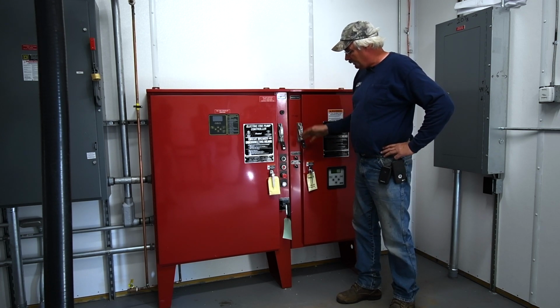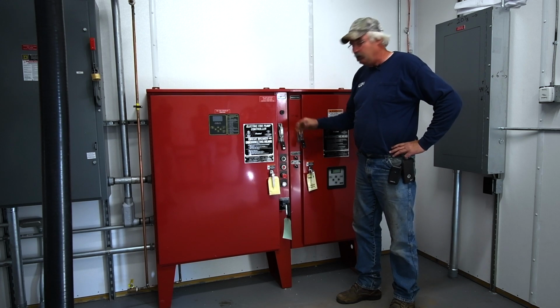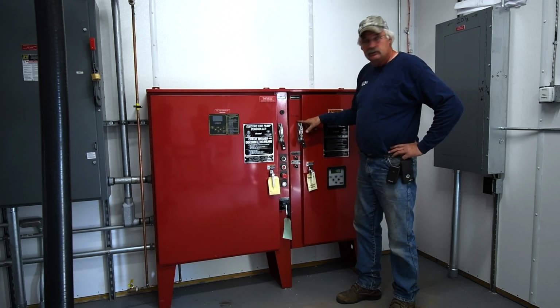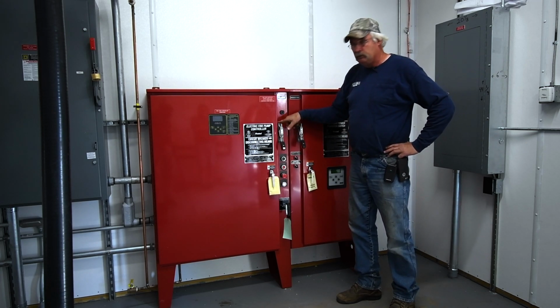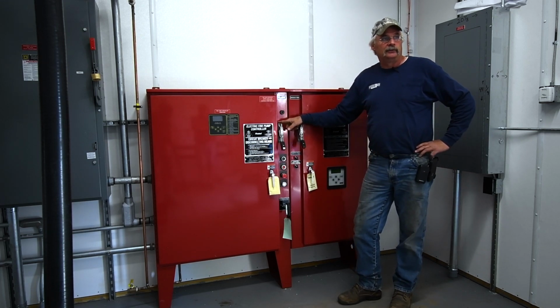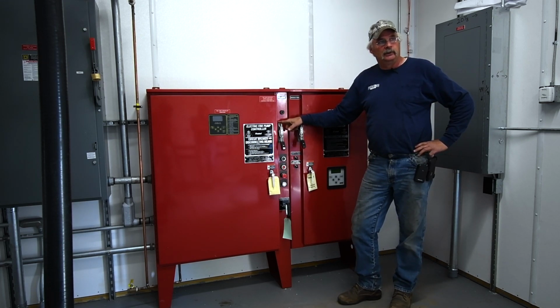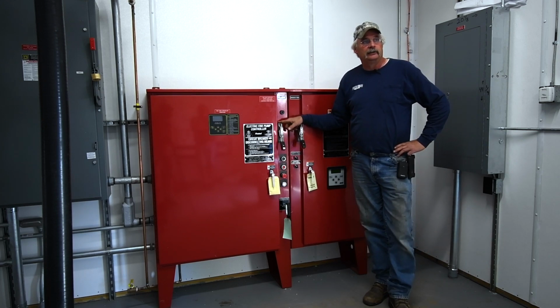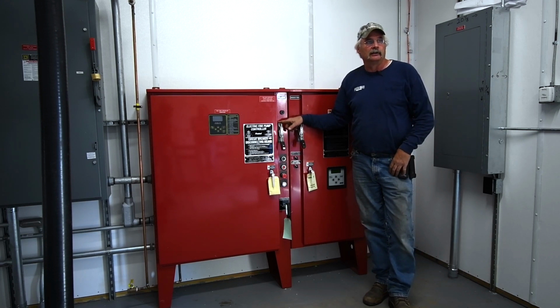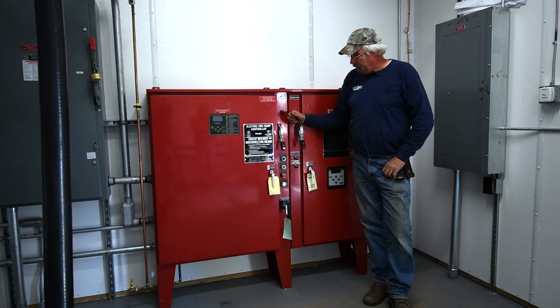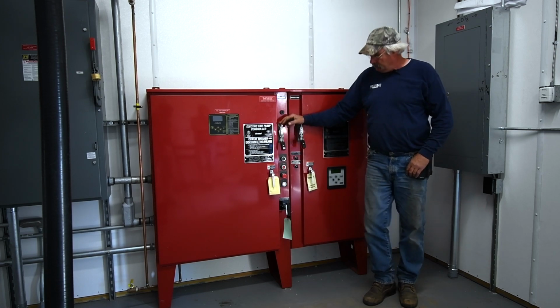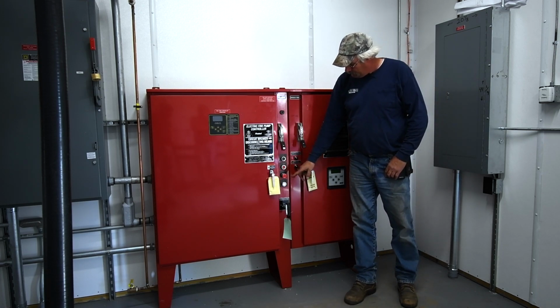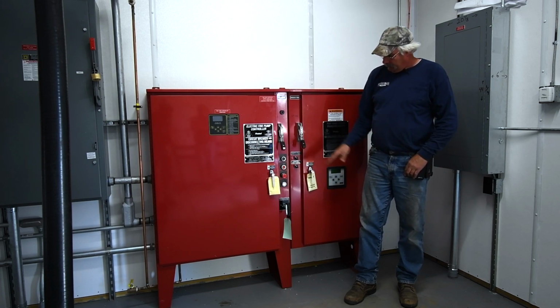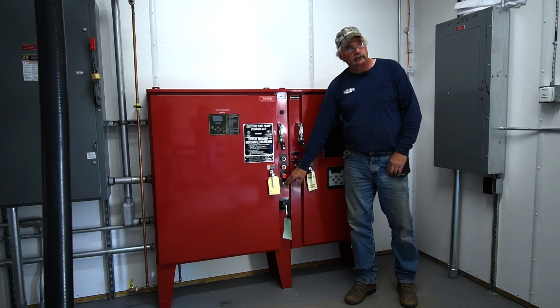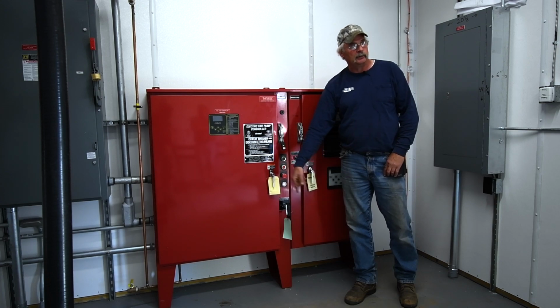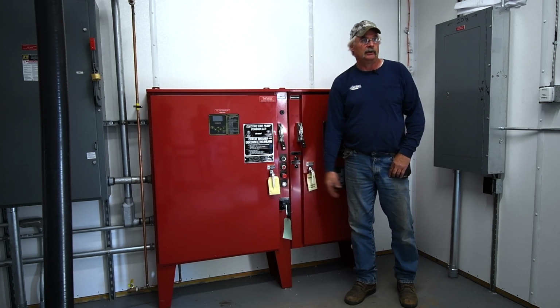But in order to shut this off so you don't start your diesel generator once they're on, you have to shut off your diesel side first and then your AC. If you shut your AC off first, it's automatically going to represent power failure, which is going to kick that diesel generator on. So again, this cabinet has a start, a stop, emergency stop, and a test. You can hit this button to test your pump. It'll automatically run for 10 minutes and shut itself right back off.